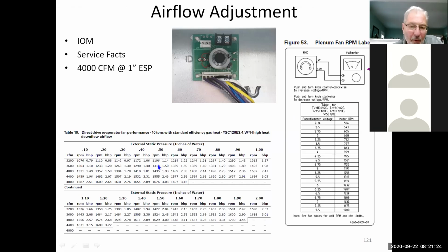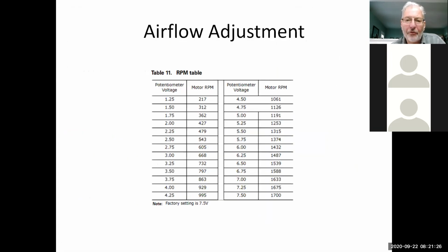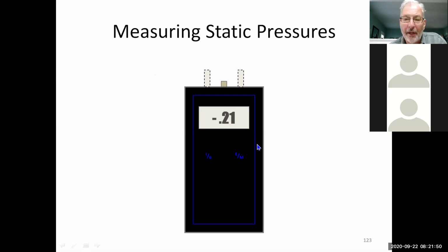So if we take our static pressure readings, and we look at DC volts, we can run these motors anywhere from 217 RPM all the way to 1700 RPM. They come programmed for Trane and American Standard at 5 to 7.5. So our range is going to be 1191 to 1700 based on the DC voltage. Okay. And how do we get there?